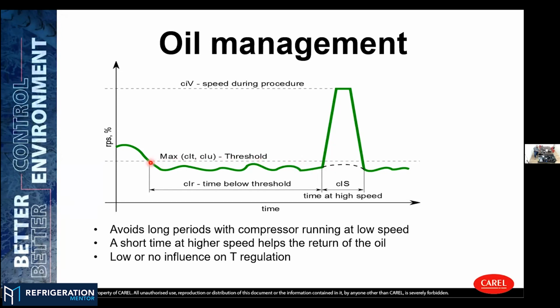If I'm not wrong, it comes at 60 minutes running at speed below 45%. So you will accelerate the compressor at 80%, something like that, for like 1 or 2 minutes. Just a rough estimation of parameters, but it's not something that will make very unstable conditions, just to make sure that you are dragging back oil to the compressor. Yeah, because you need oil at the compressor.